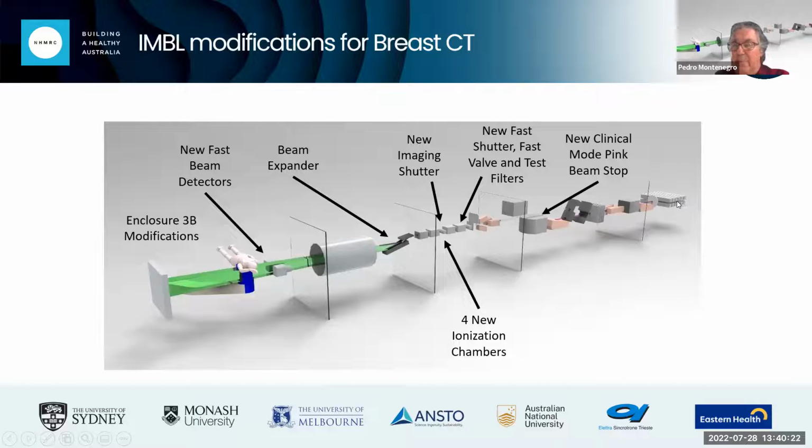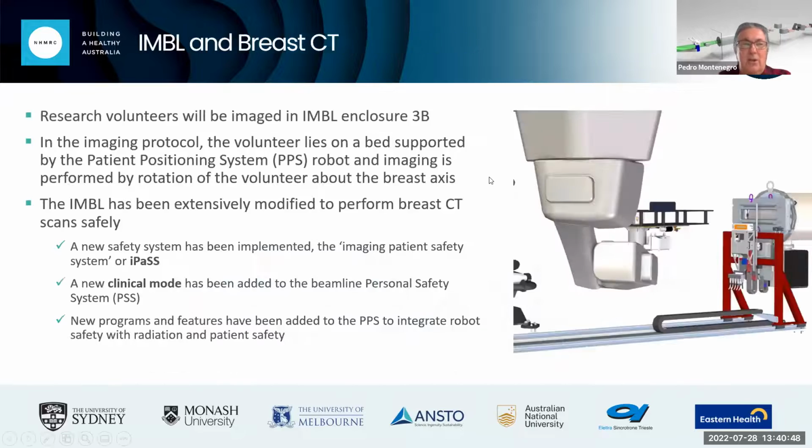And that means, of course, all the beamlines lose their X-rays because the whole storage ring goes down, but that can happen in 20 milliseconds. So this is the last resort. So basically we have 4 levels of safety in terms of how many shutters we can close, but this is the very last one. If everything went terribly wrong, we still would rely on this to close the beam.